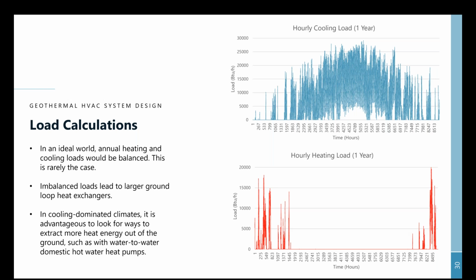Well, how does that impact the design of a ground loop heat exchanger? What it does is it says you're going to need a much bigger heat exchanger, because when you are rejecting all of this energy to the ground, you need to spread it out over a larger area so that you don't cause the permanent buildup of heat within that ground source. So for cooling dominant climates, we're always looking for ways to extract more heat out of the field.